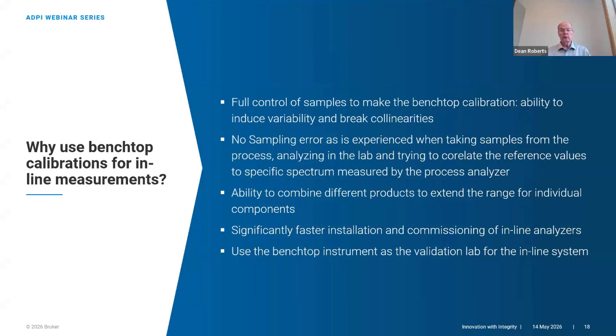Number one is developing the calibrations. We already have mature calibrations for the variety of the dairy products that we're measuring on our Benchtop instrument. So we're doing cream, we're doing milk of all the different varieties. We're looking at whey products, we're looking at ice cream premix, we're looking at the dressings for cottage cheese, we're looking at the base for doing sour cream. All of those things are liquid. Because of the larger path length, we can pump them through the instrument without any problems, and the calibrations are quite nice. But we also then have the ability to spike samples or be able to change the relative concentrations of the constituents in the sample. And that is done to break up collinearities and make a more robust calibration.